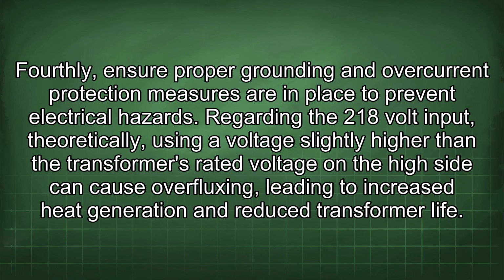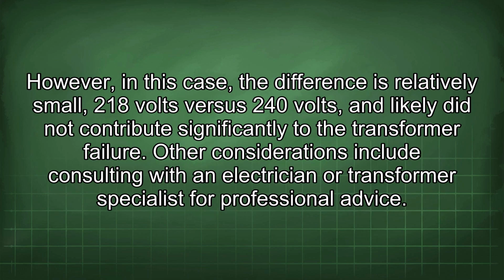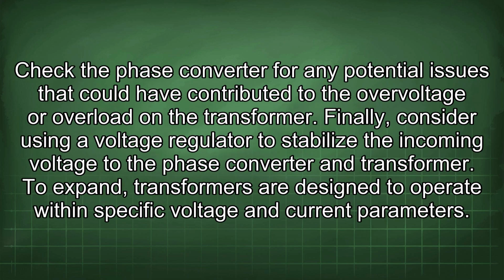Regarding the 218 volt input, theoretically, using a voltage slightly higher than the transformer's rated voltage on the high side can cause overfluxing, leading to increased heat generation and reduced transformer life. However, in this case, the difference is relatively small, 218 volts versus 240 volts, and likely did not contribute significantly to the transformer failure. Other considerations include consulting with an electrician or transformer specialist for professional advice. Check the phase converter for any potential issues that could have contributed to the overvoltage or overload in the transformer. Finally, consider using a voltage regulator to stabilize the incoming voltage to the phase converter and transformer.